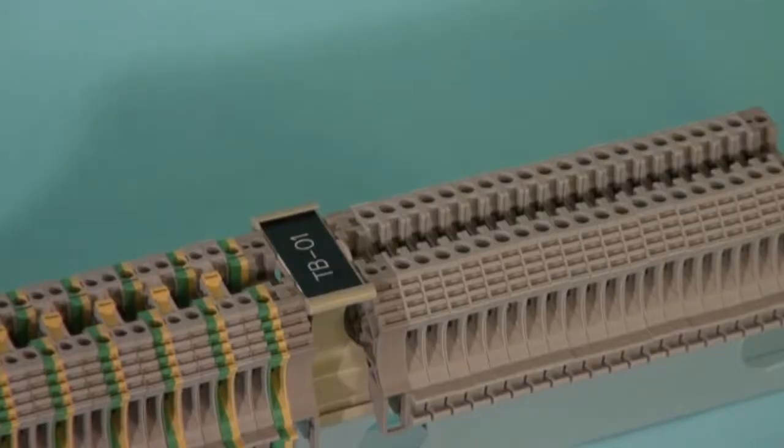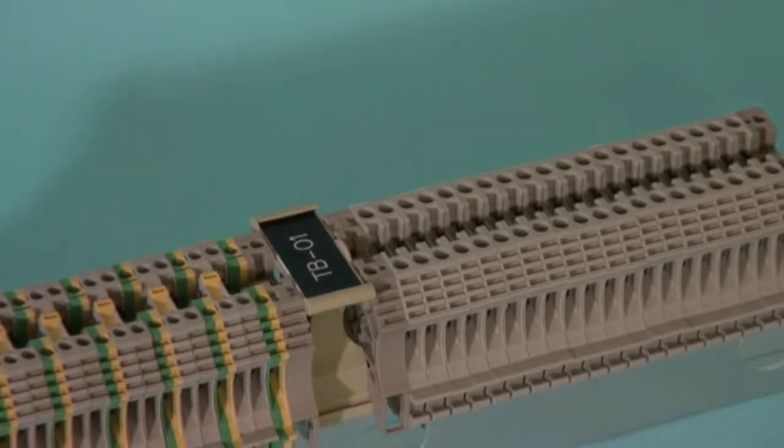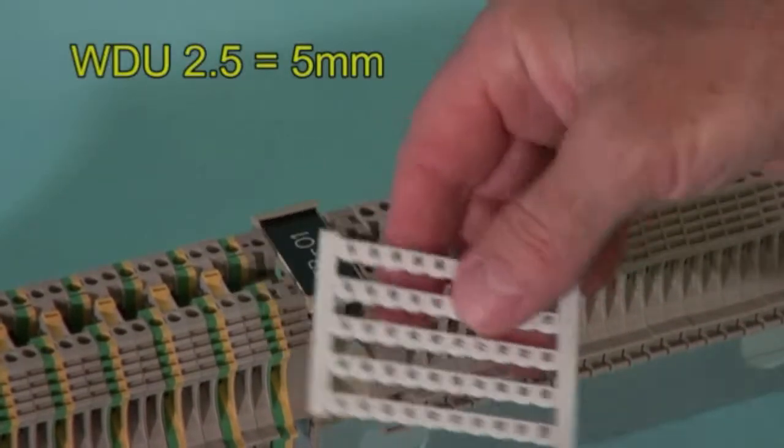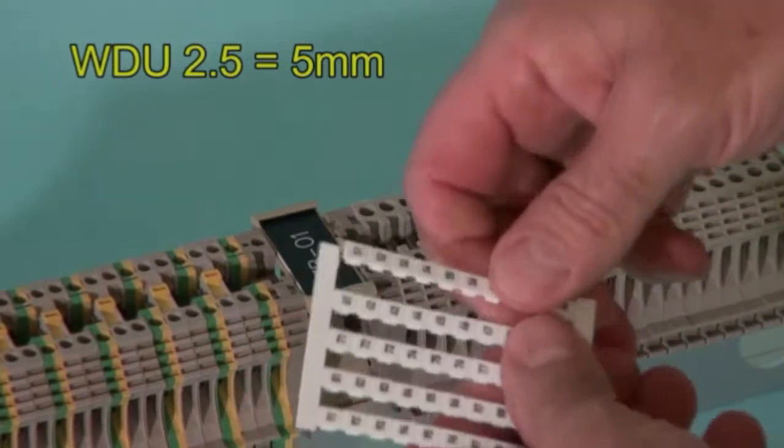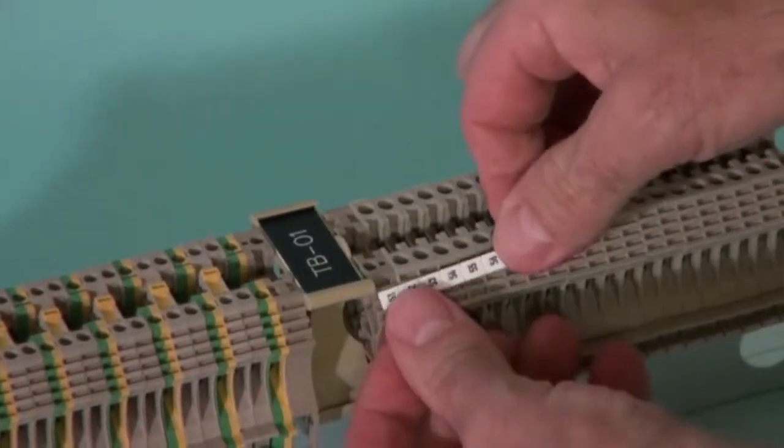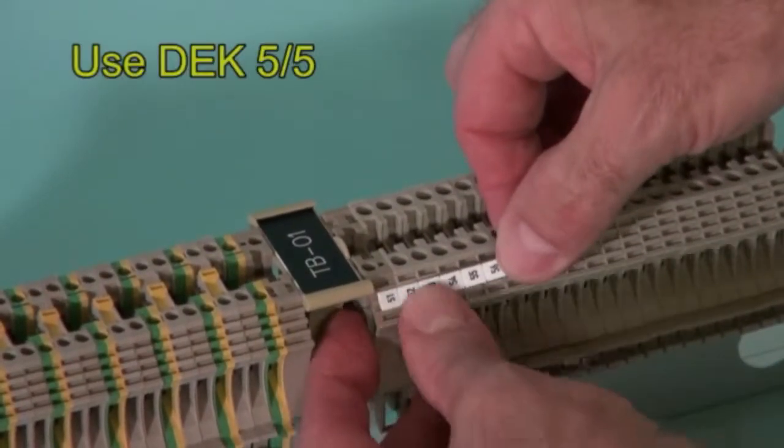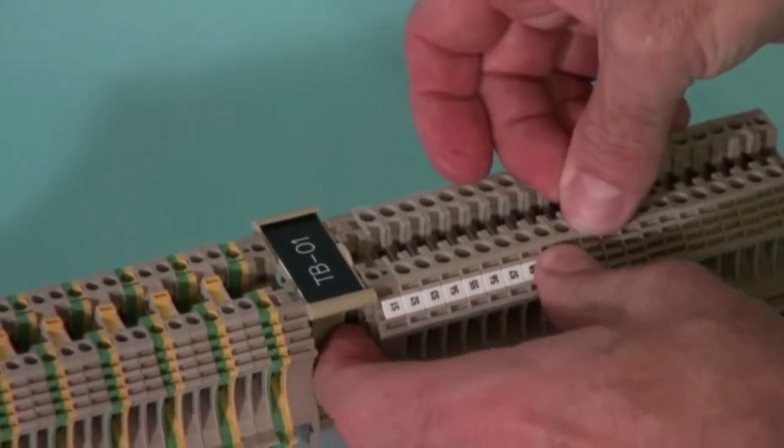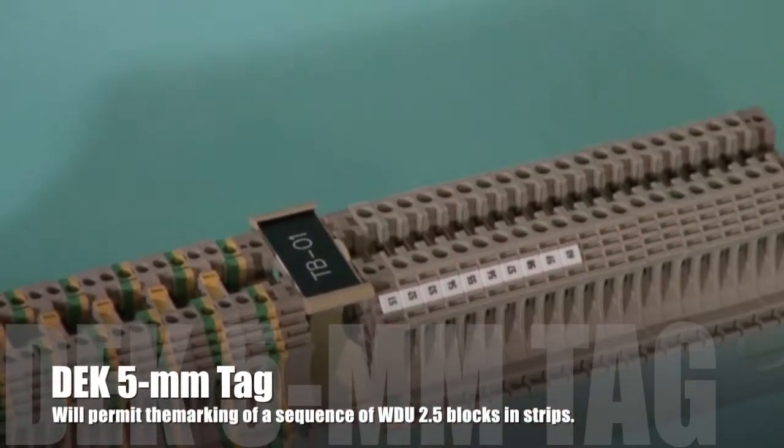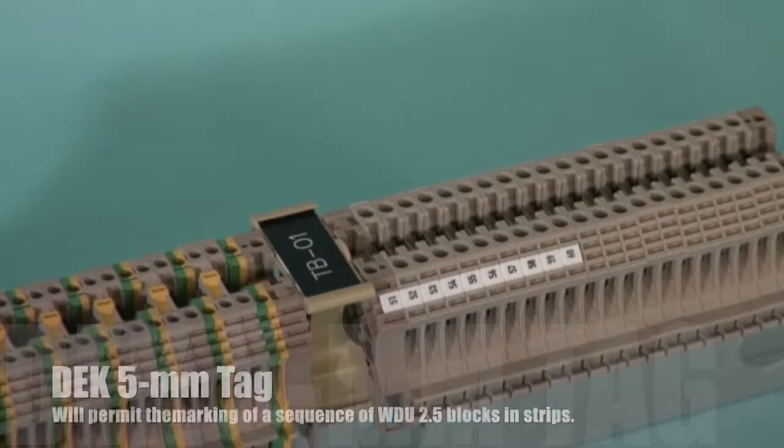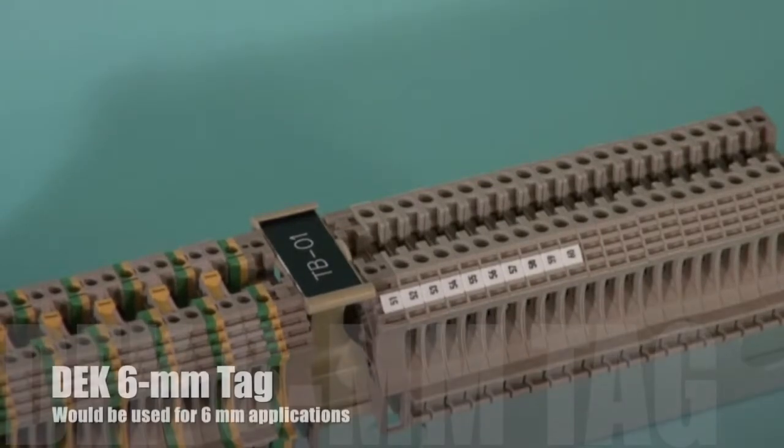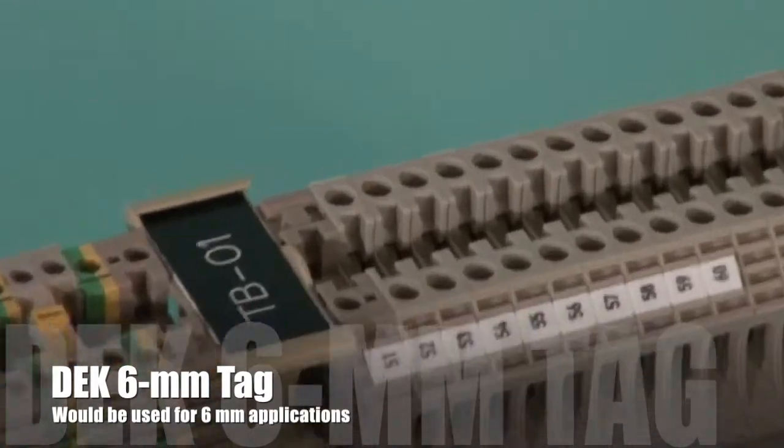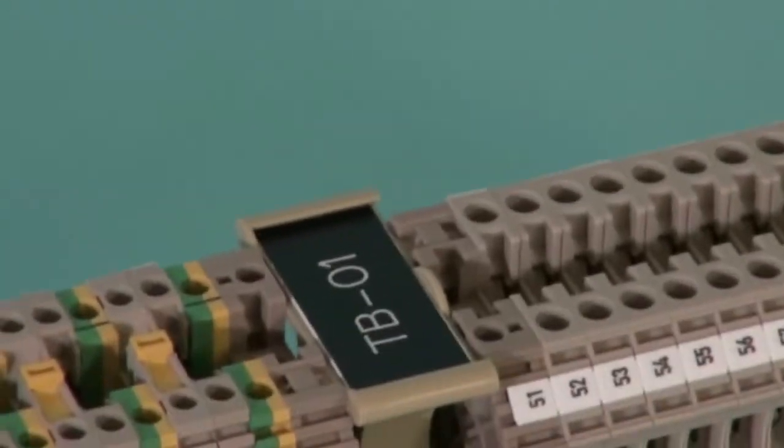Generally, the tag width will be chosen to match the width of the terminal block. For example, a WDU 2.5 is 5mm thick, so a DEK 5 5mm tag will permit the marking of a sequence of WDU 2.5 blocks using strips. Similarly, a WDU 4 is 6mm wide, so a DEK 6 would be used.